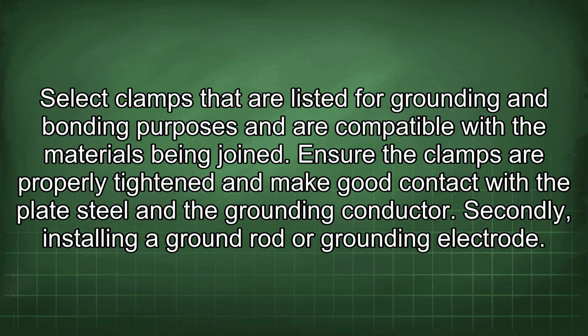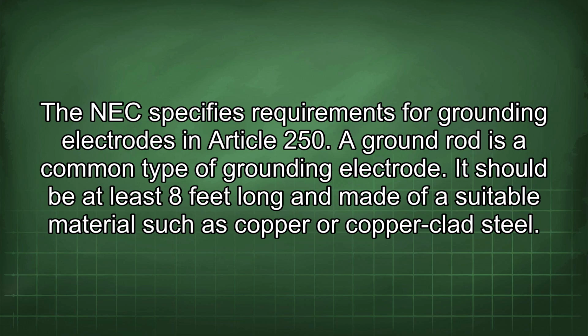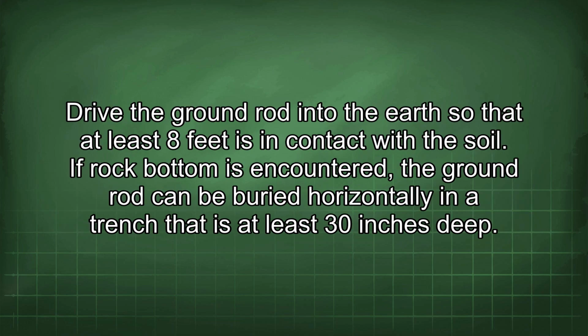Secondly, installing a ground rod or grounding electrode. The NEC specifies requirements for grounding electrodes in Article 250. A ground rod is a common type of grounding electrode. It should be at least 8 feet long and made of a suitable material such as copper or copper-clad steel. Drive the ground rod into the earth so that at least 8 feet is in contact with the soil.